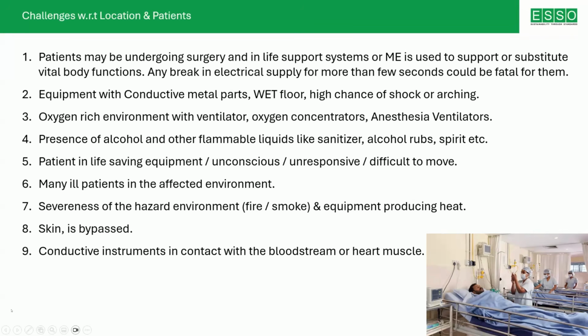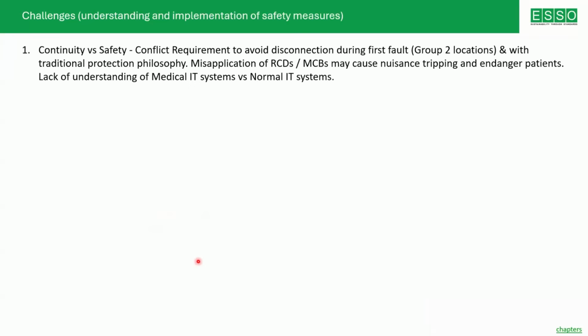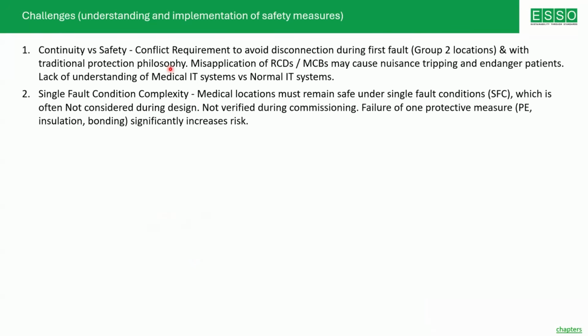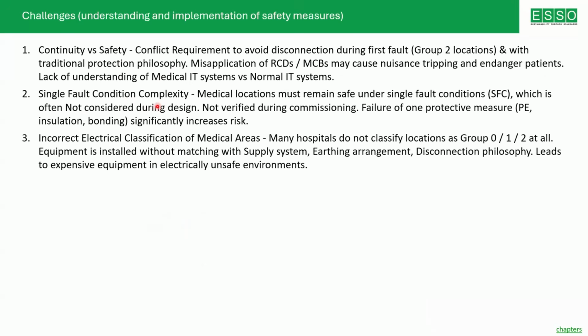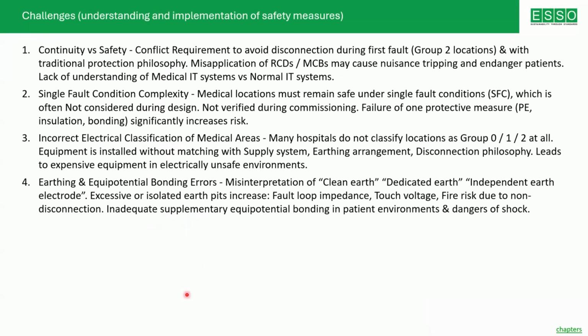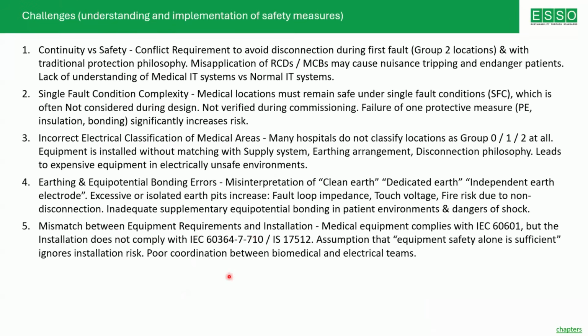Then the equipment have conductive metal parts. There are wet floors, a high chance of electric shock and arcing, an oxygen-rich environment, presence of alcohol, patients on life-saving equipment, many ill patients in the affected environment, and the severity of the hazard with respect to fire and smoke is very high. Skin is bypassed, and conductive instruments are in contact with the bloodstream of the patient. So continuity and safety of the electric supply is very much essential. Also, handling faults and continuity of supply during a single fault condition is a little bit complex.